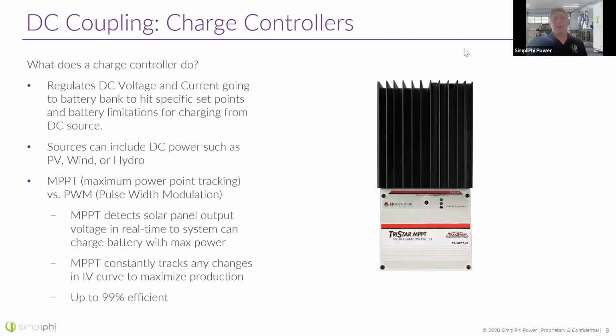All right, so what does a charge controller do? How does it work when you're DC coupling? First off, a charge controller is going to regulate that DC voltage for charging the bank and, if needed, limit the current that's going into the battery bank. This is going to hit specific set points that you've often programmed into the controller as the user. And usually most charge controllers can accept any DC power source such as PV, wind, or even hydropower.